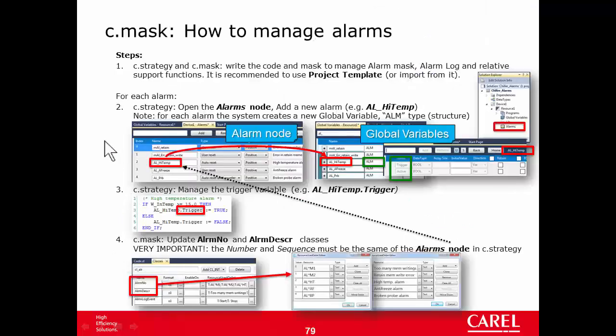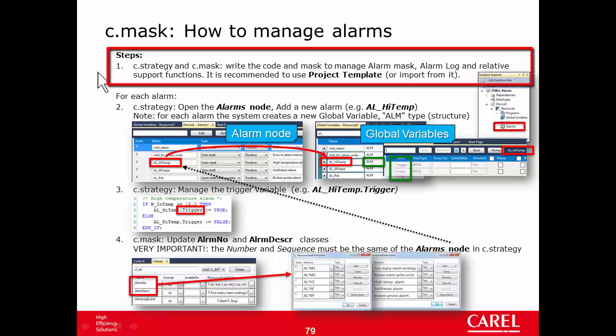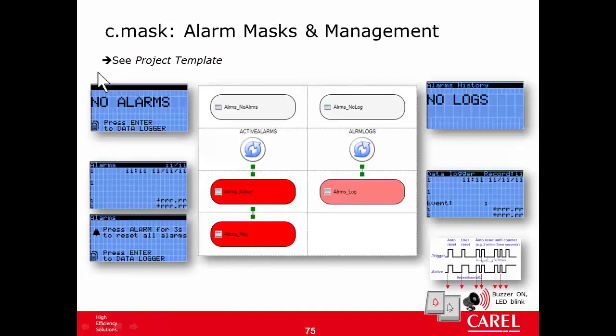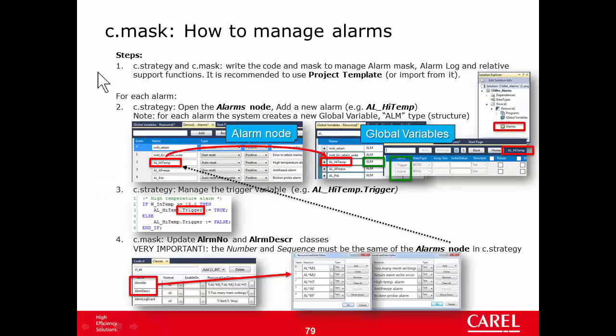As usual, there is a slide that summarizes the steps to follow to manage the alarms. Step one: in C-Strategy and in C-Mask, we have to write the code and mask to manage the alarm mask, the Alarm Log, and all the support functions. The suggestion is to start from the project template because it already has these five masks inside and everything else. The chiller alarms project is based on the project template, so step one is done.